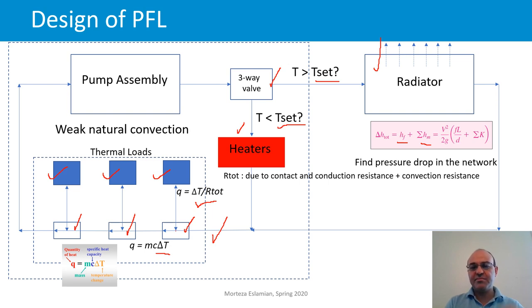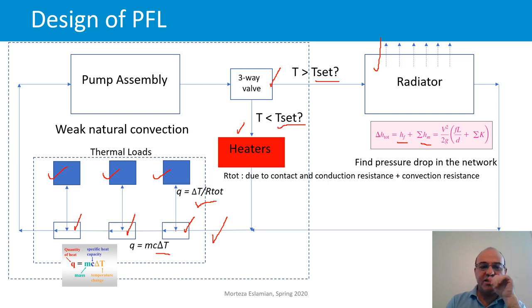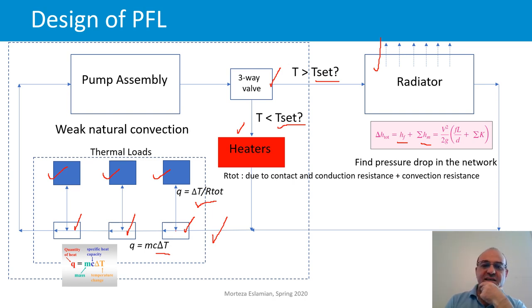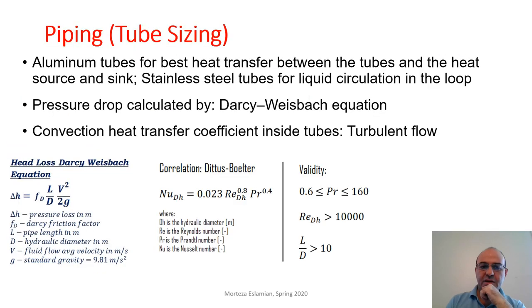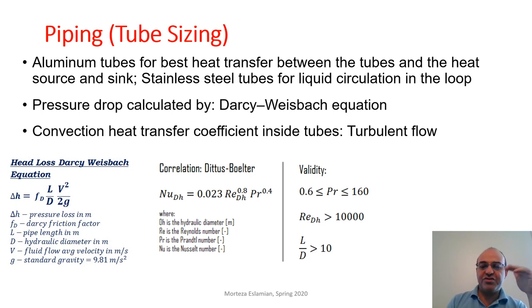Based on the set Reynolds number — which defines the fluid velocity in the pipes — we can calculate the flow rate. With the flow rate we can calculate the pressure losses, plot the system curve for the pump, and then decide the normal operating point of the system and choose the pump accordingly. Additionally, aluminum tubes are used for heat transfer between tubes and heat sources or heat sinks because they have low thermal resistance. Stainless steel tubes are used for the rest of the loop connections where heat transfer is not the goal.